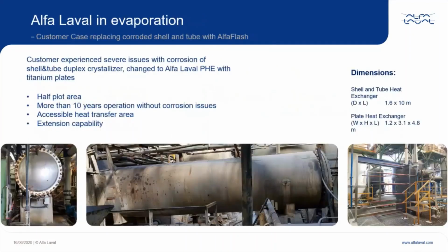Finally, I will present a customer case which highlights the importance of selecting the correct materials and also confirms that plate and frame technology will work for crystallizing duties. This ZLD plant is located in northern Spain, and the owner, a Spanish waste management company, experienced repeated issues with corrosion of a duplex stainless steel shell and tube heat exchanger. The unit, which was supplied by another manufacturer, was operating as the second effect in a two-effect evaporation system intended to provide zero liquid discharge of mixed oily wastewater.